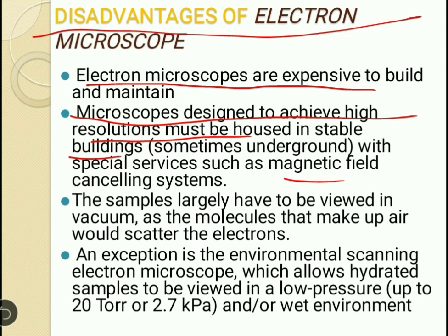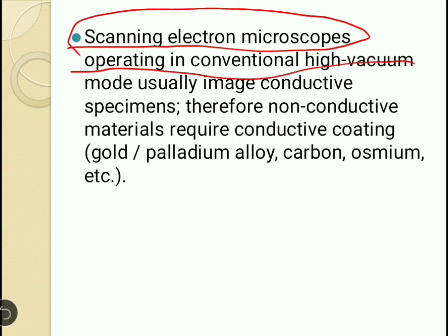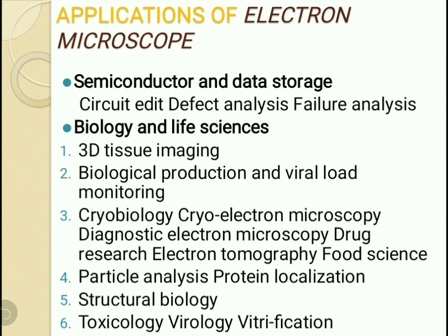So these are the various disadvantages in the procedure. Then an exception is the environmental scanning electron microscope, which allows hydrated samples. So in SEM we can use hydrated samples at a low pressure and wet environment. Now the scanning electron microscope also has some disadvantages. Operating in the conventional high vacuum mode, it usually images conductive specimens only. Therefore non-conductive materials require conductive coating such as gold, palladium, carbon and osmium. So these are some disadvantages.